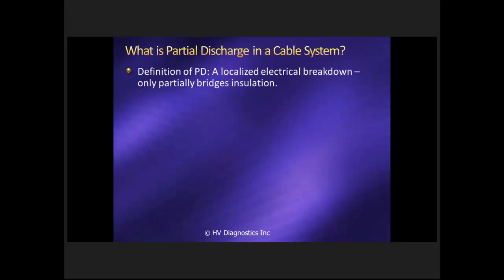Partial discharge, the definition of it, is a local electrical breakdown that only partially bridges the insulation. So you can get partial discharge in anything from generators, motors, switchgear, transformers, etc. We're dealing with cables now, but the same applies here. So a partial breakdown of the insulation of the cable. And it's important to know that partial discharge doesn't by itself collapse the voltage of the cable, so we don't have a dielectric failure.